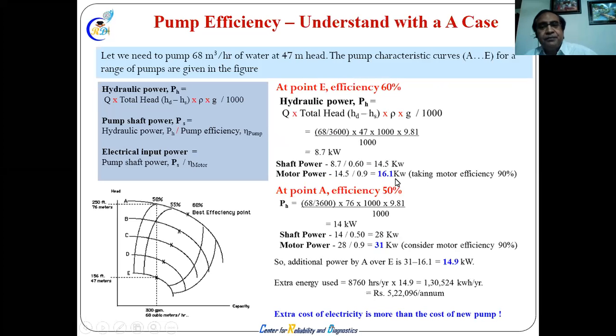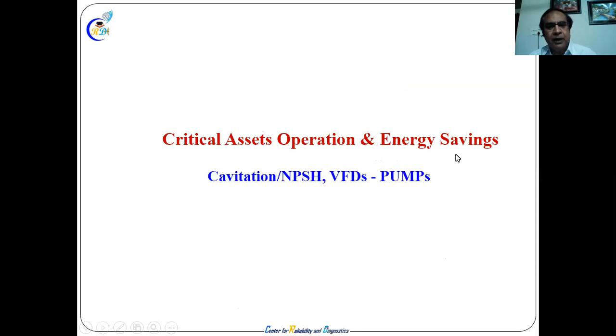It comes around 31 kilowatt. So instead of a 16 kilowatt machine, we get 31 kilowatt. For 50%, we have to put in a motor of higher capacity, and that means loss. Higher capacity means loss. So we have to take care of the pump efficiency, and that is the thing you have to understand in this case.